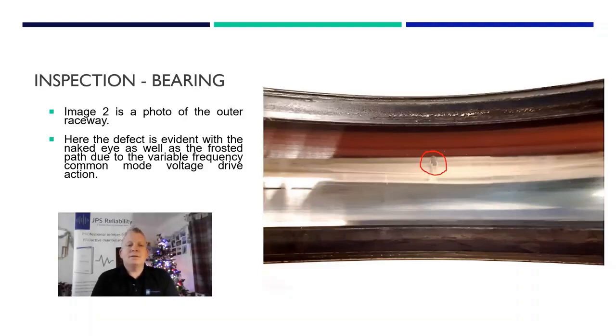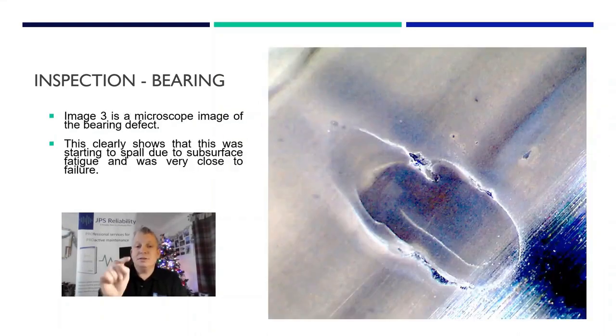Hi, welcome back. So we've looked at the bearing and we looked at the tools which we can use to additionally quantify this electrical anomaly. And what you can see here, if you see that grey band coming up and down, it's getting thicker in the load zone of the bearing. And that grey frosted look is from the common mode voltage from the drive. And as we showed you, there's that tiny little fleck in there. And if we zoom in to the fleck, you can see a little bit of spot welding, and it's all subsurface fatigue, so that's going to crack and that's going to pop off.